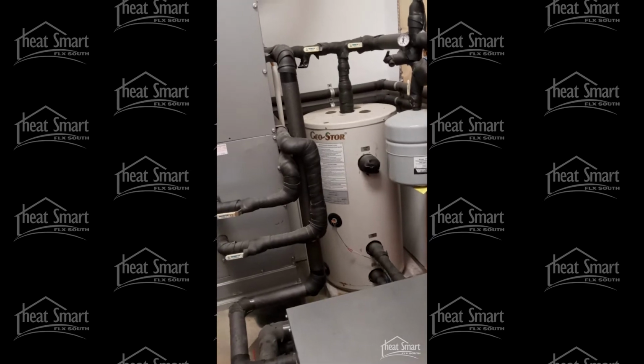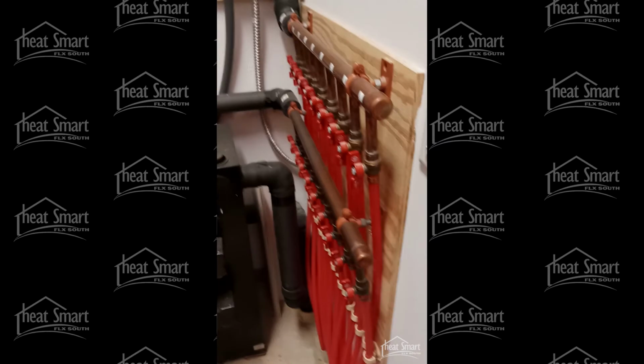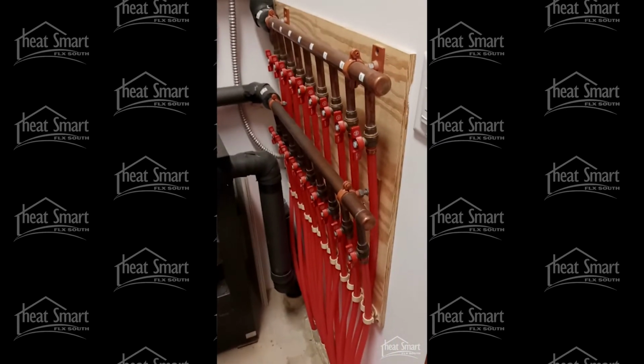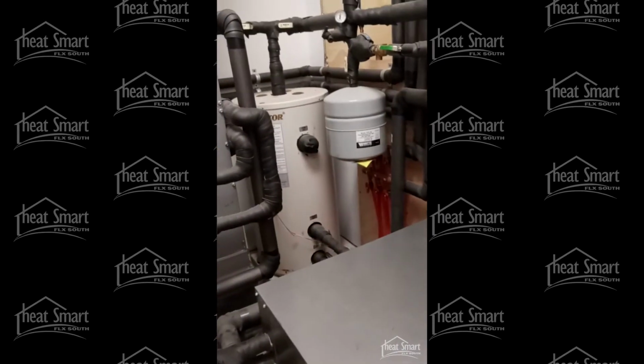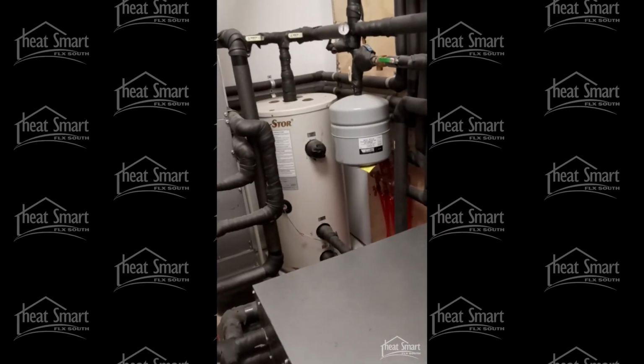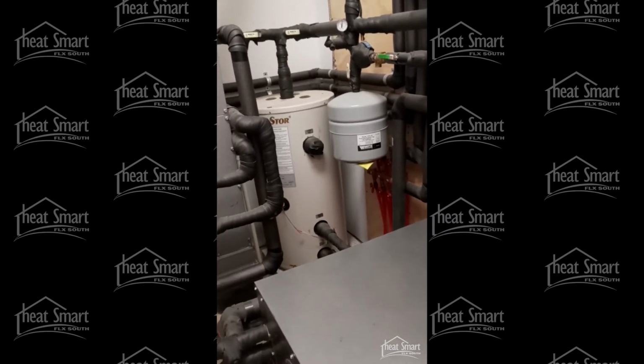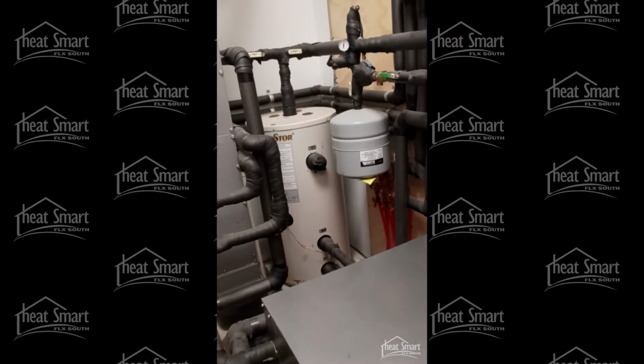When the water circulates through these radiant floor heat tubes, these red things, you get the heat from the buffer tank, which stores the heat because the heat pump can't heat the water fast enough. You need that buffer tank as an intermediary to store it. All it does is circulate water through the floor, through these tubings, when the zone valves kick on. And that's how you heat the house, or heat the library here.